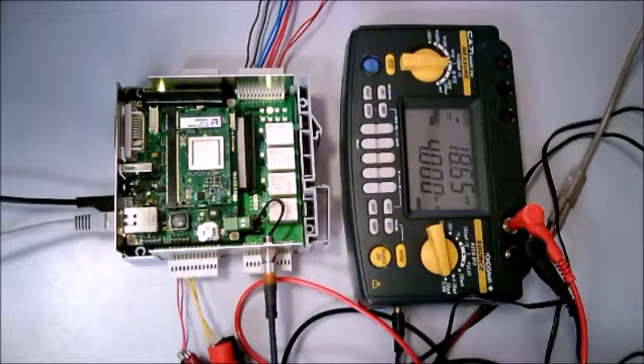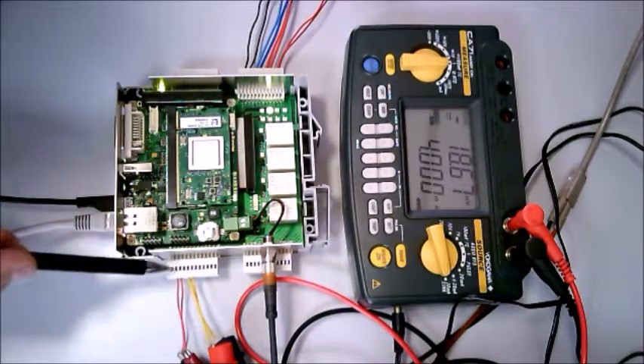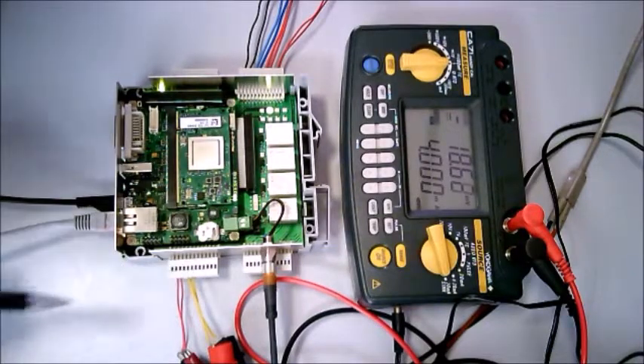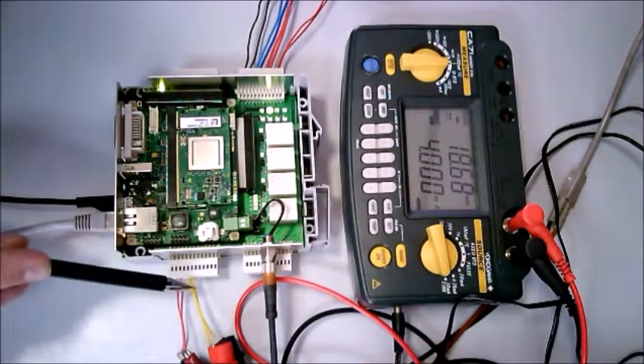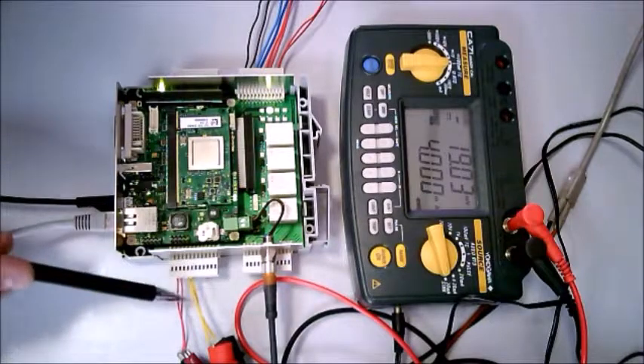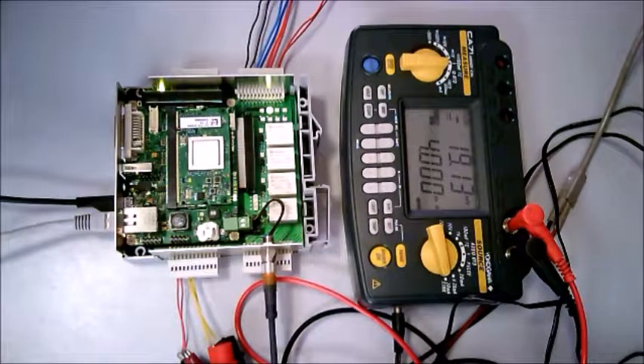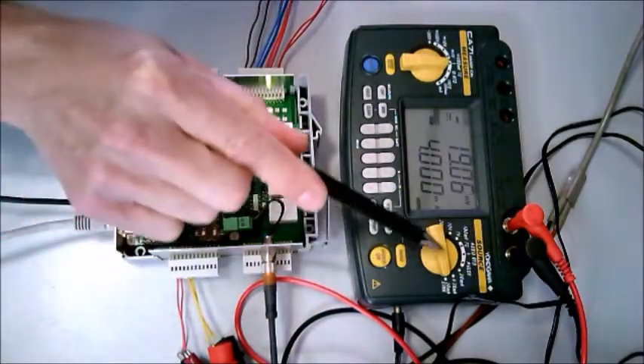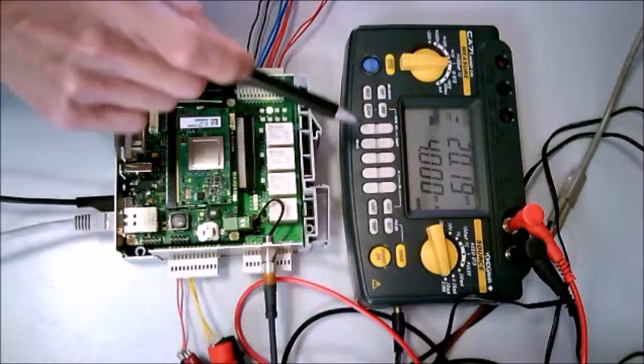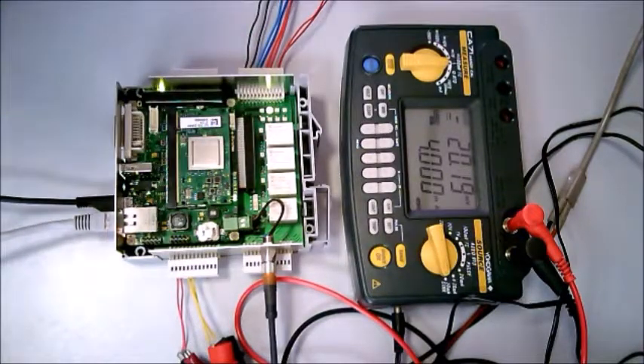Okay, so we suppose we have already connected the different inputs to be calibrated. Here we can see the connector of the 4 analog inputs. In this case we have connected a couple of them, the analog input 0 and the analog input 1, the first and the second of the 4 available channels. Here what we have is a precision accurate calibration multimeter that will generate the 4 to 20 milliamp input signal.